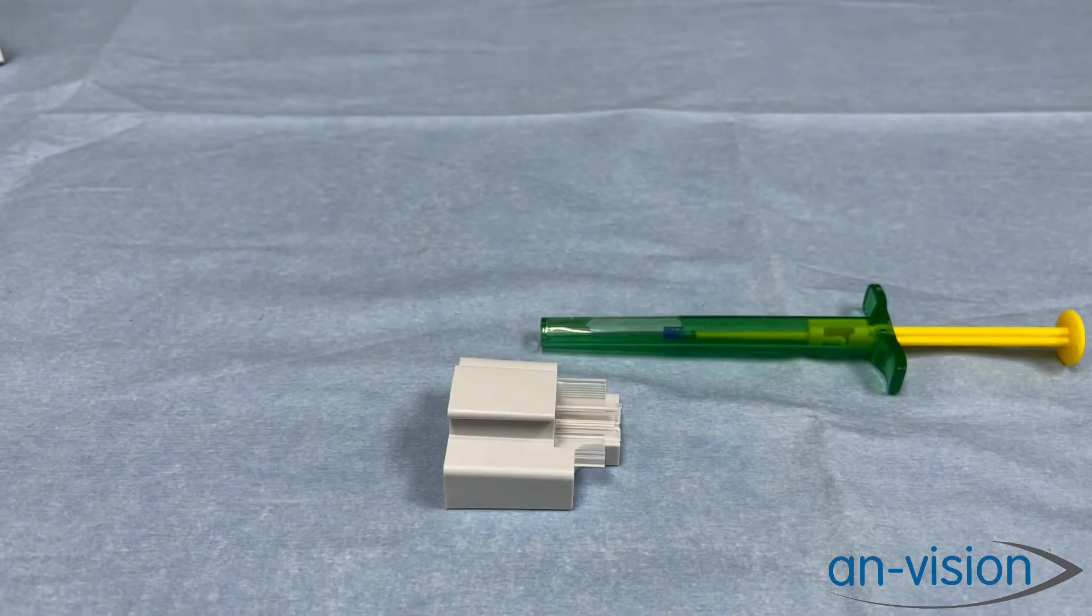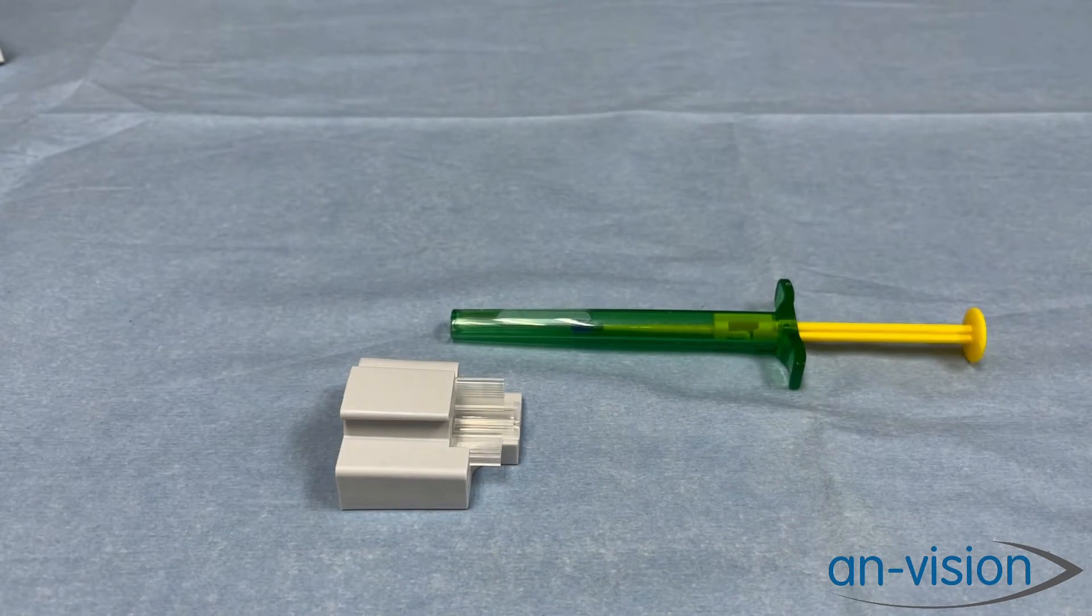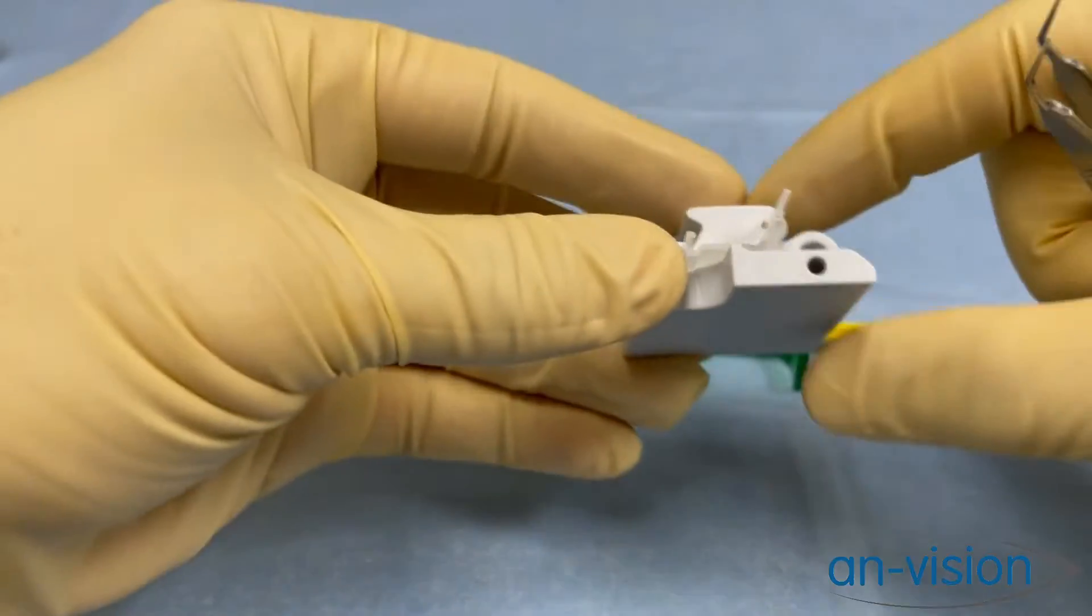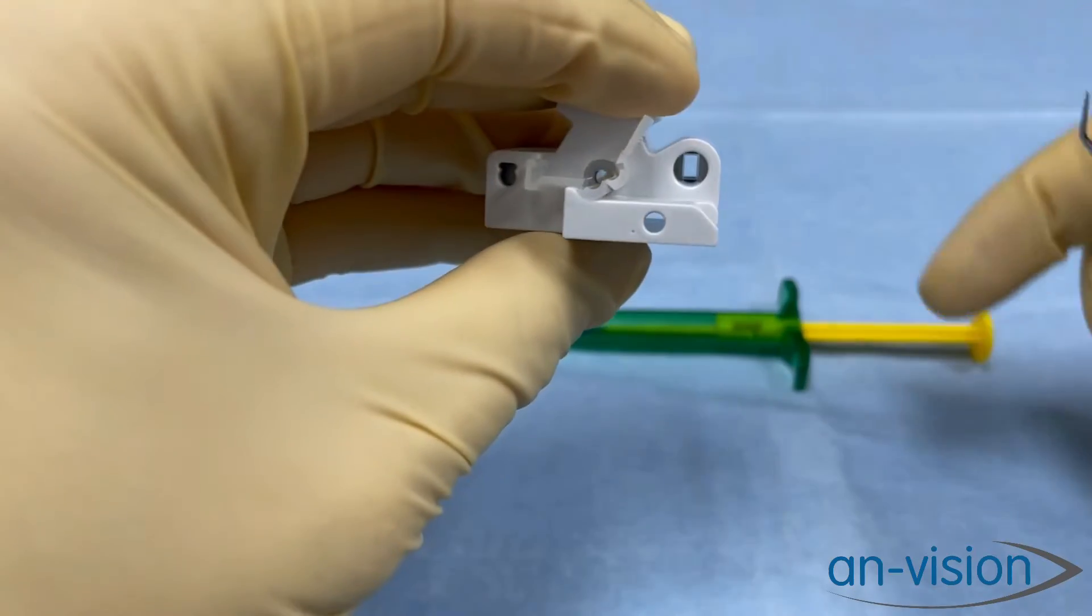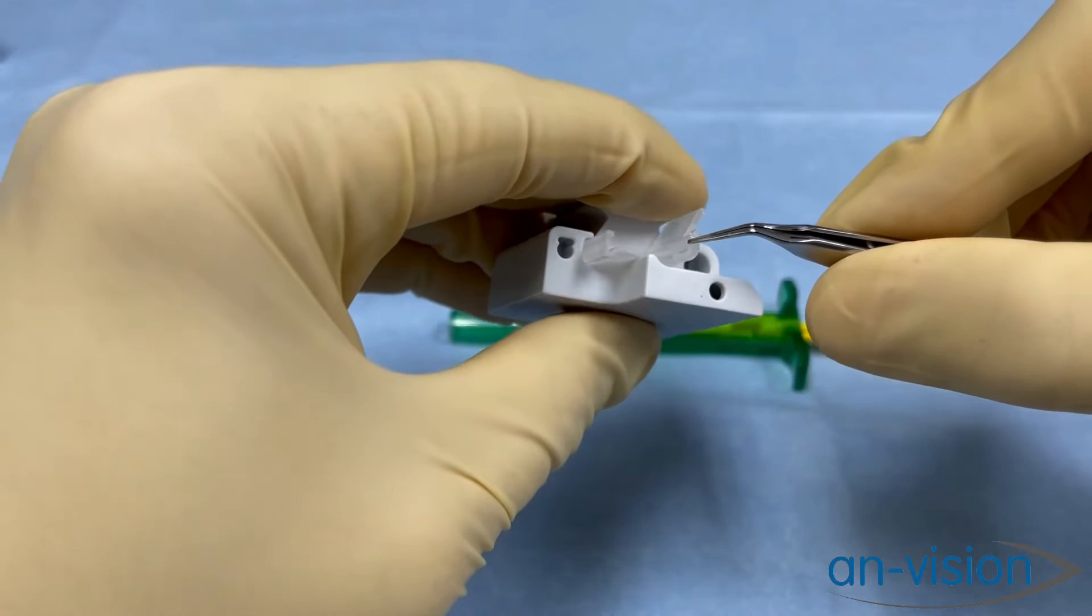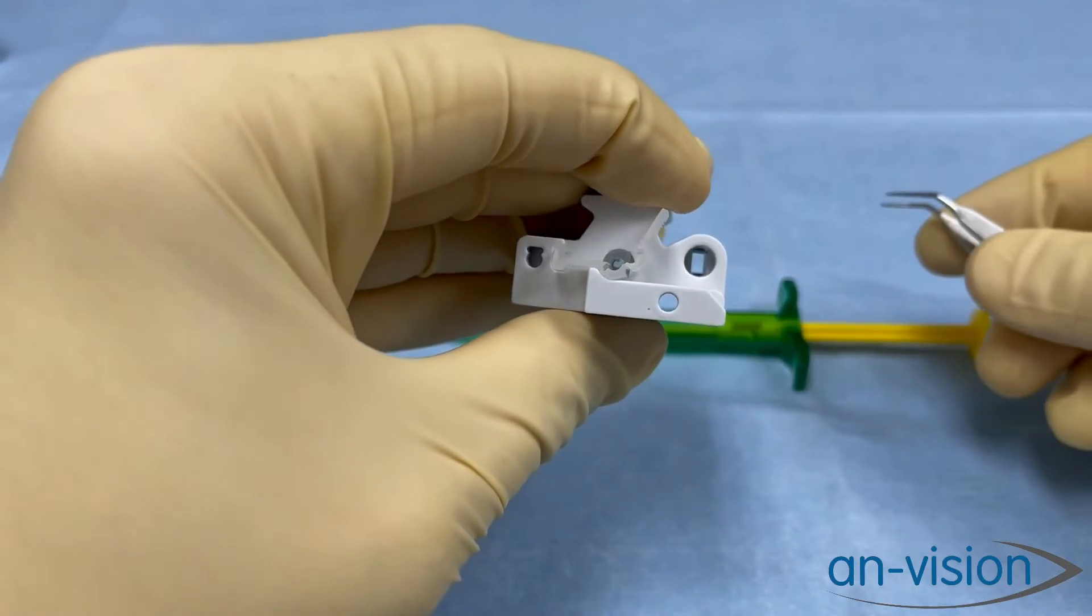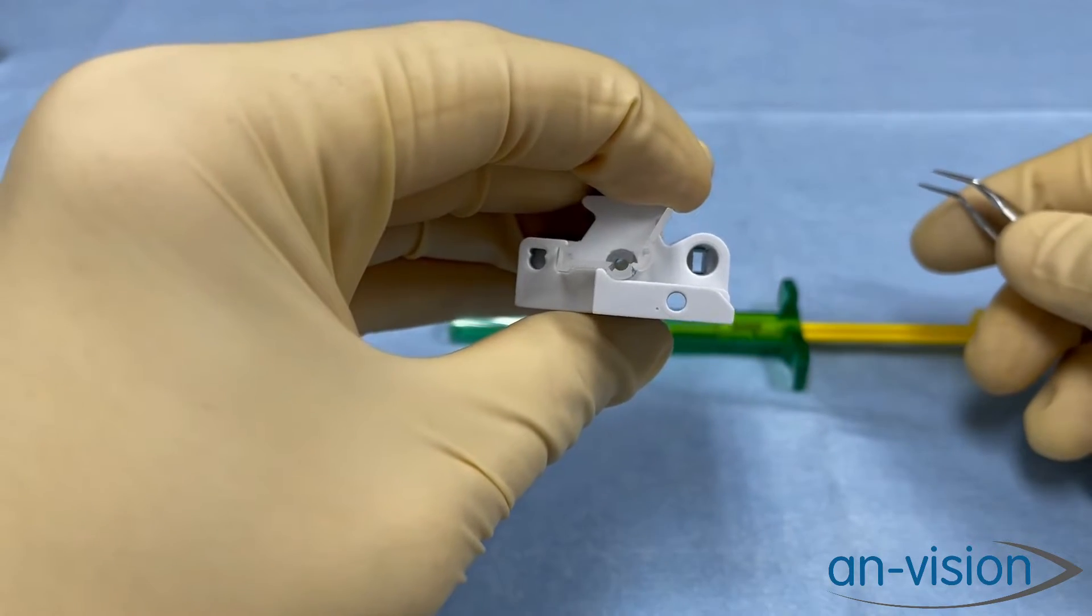Now, when we are loading an IOL into the Viscoject Easy, one thing we want to remember is in the loading chamber, there are grooves set in the base.